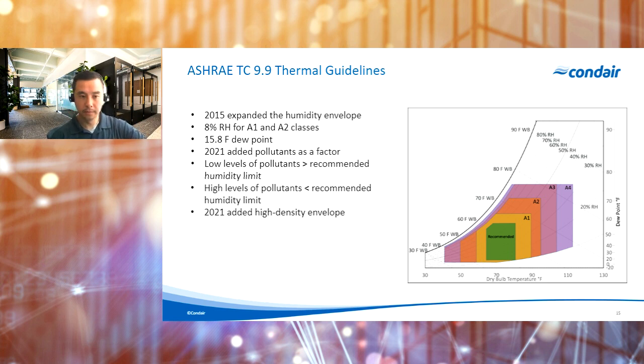In the recommended envelope, it's actually not a relative humidity at the bottom. It's a dry bulb. So it's 15.8 degrees Fahrenheit dew point on the lower end. They'll go into the allowables. The lower relative humidity rate is 8% RH. That being said, this is guidelines. The specific recommendations for relative humidity and temperatures really have to be a coordinated effort between the IT equipment manufacturer and the facility operator. We did go into a lot more detail of this in the webinar that Will has mentioned previously.